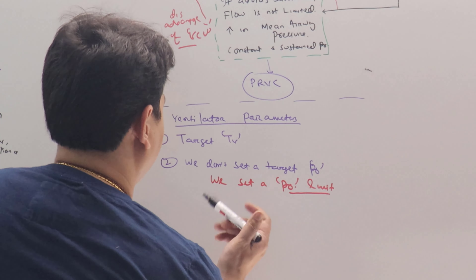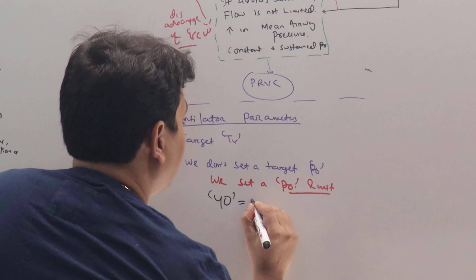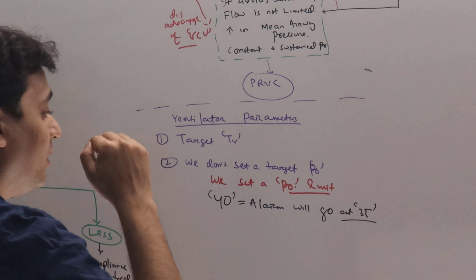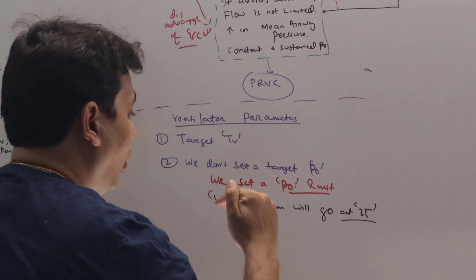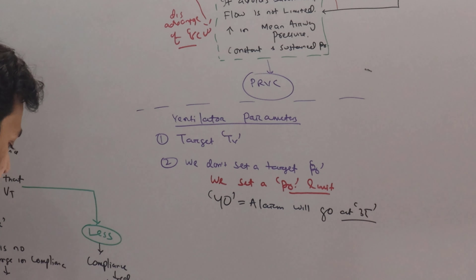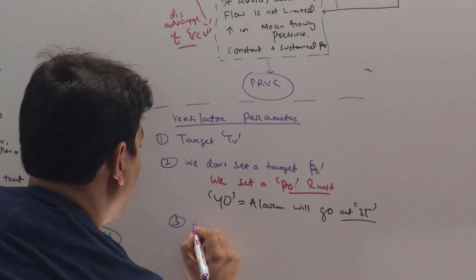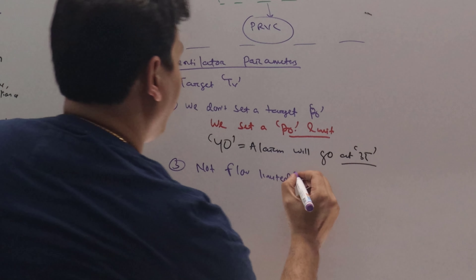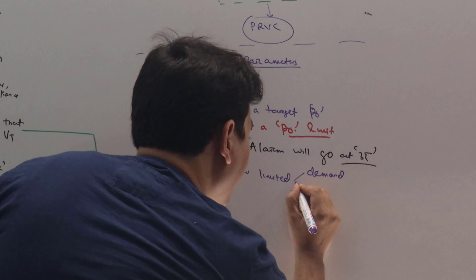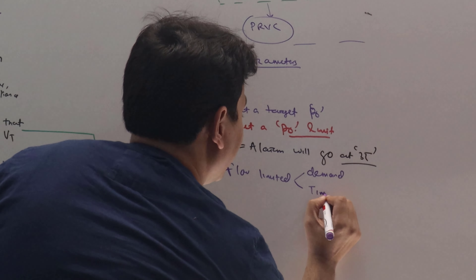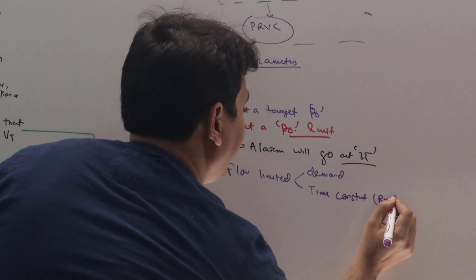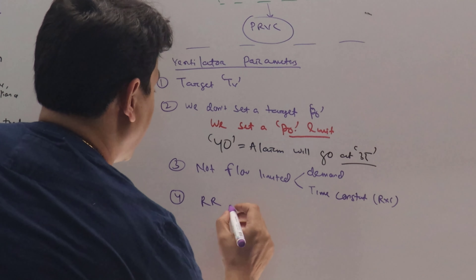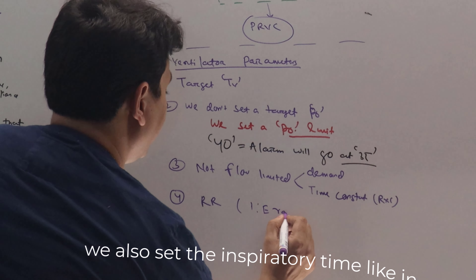For example, if we set a pressure limit of 40, then the alarm will go off at 35. This you have to remember: the safety limit is 5 mmHg below the pressure limit that you set. Number three, it is not flow limited — the flow will change depending upon the demand of the patient, or if the patient is sedated or paralyzed, it will depend upon the time constant, which is equal to resistance multiplied by compliance. Then we also set a respiratory rate, which will also decide our I:E ratio.